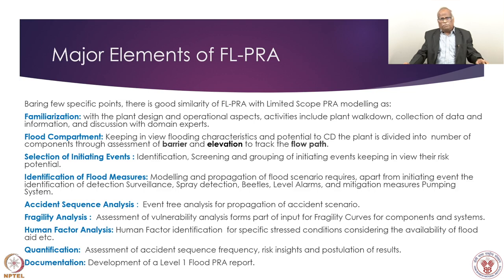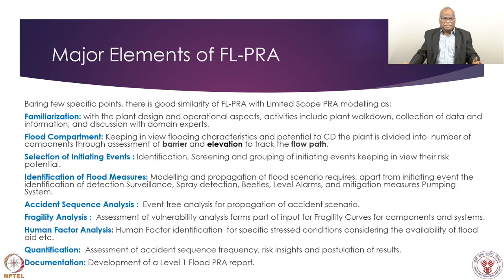How is the plant divided into compartments? Based on location and elevation — meaning if flooding occurs in one area, how will it propagate into another area or be contained? How will consequences be limited or propagate? Compartment modeling is important for areas like the emergency diesel generator site, which is critical from an emergency power failure point of view. Significance comes from there.